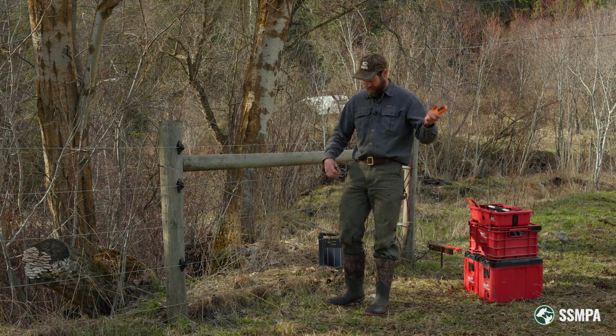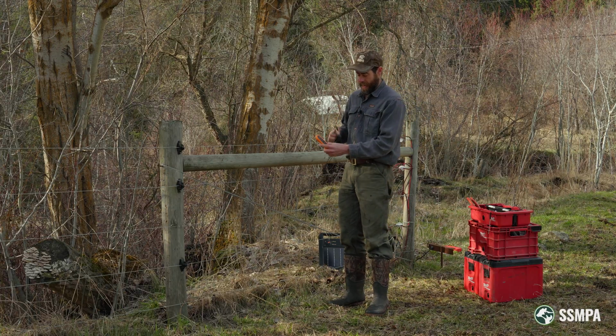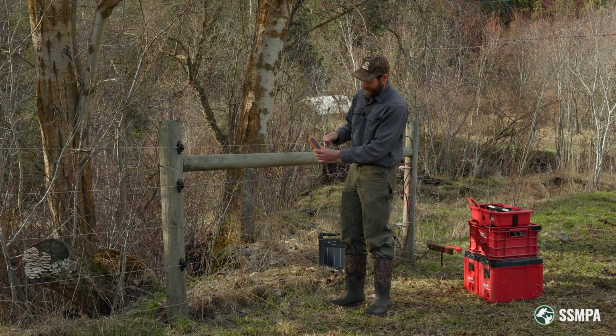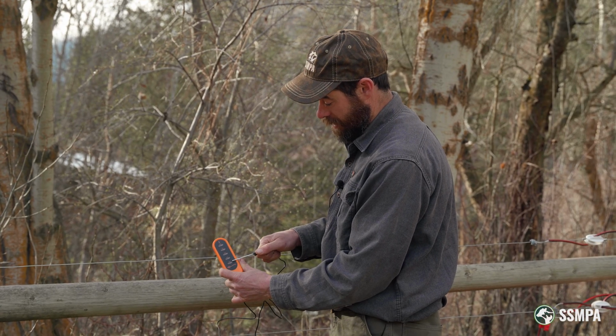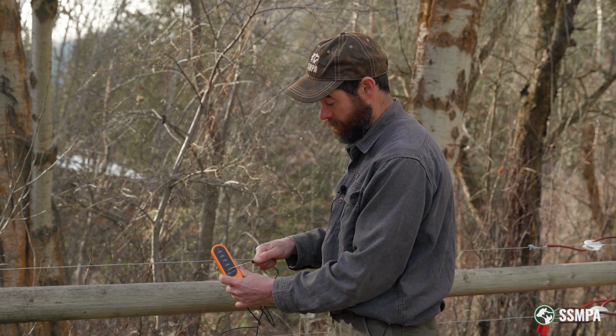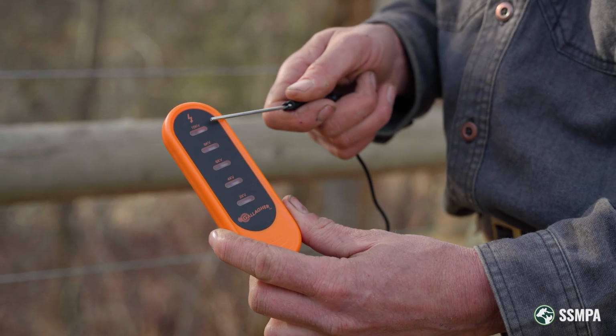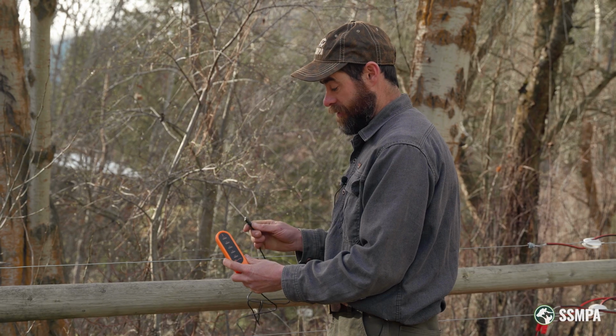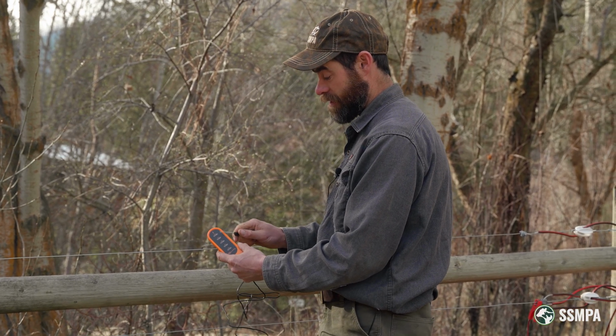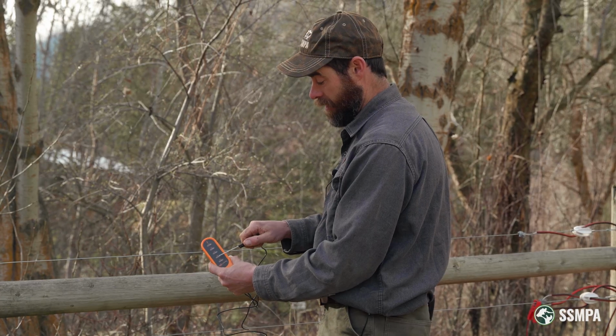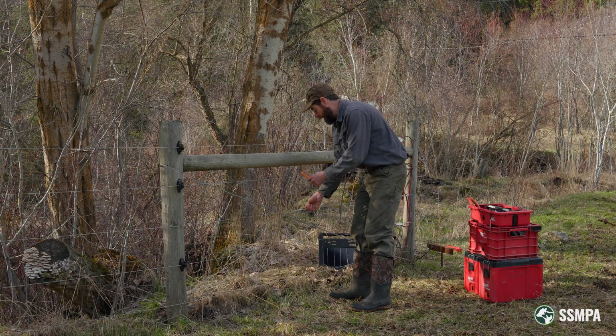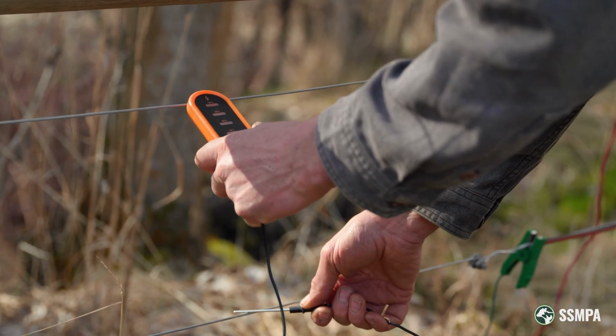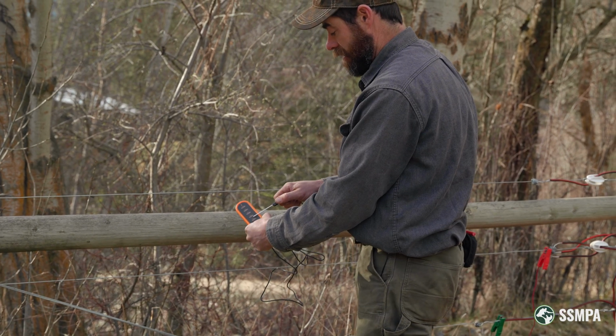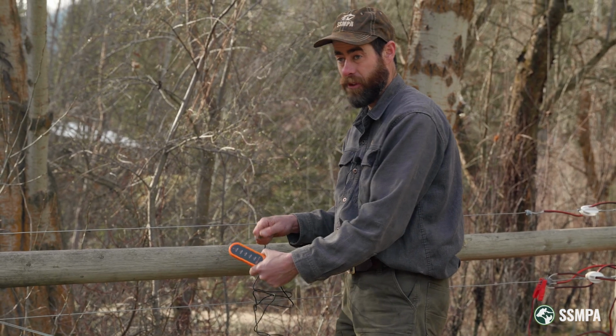The most basic, common type of tester has multiple lights, and each light will light up at a different voltage. So this one says if your fence is putting out 2,000 volts, this light will light up, all the way up to 10,000 volts for this one. This type of tester is just going to tell you the relative performance of your fence by indicating roughly in 2,000 volt increments what the voltage on your fence is. It's pretty coarse, but I can see here that the bottom two lights are flashing, so we're at least above 4,000 volts.